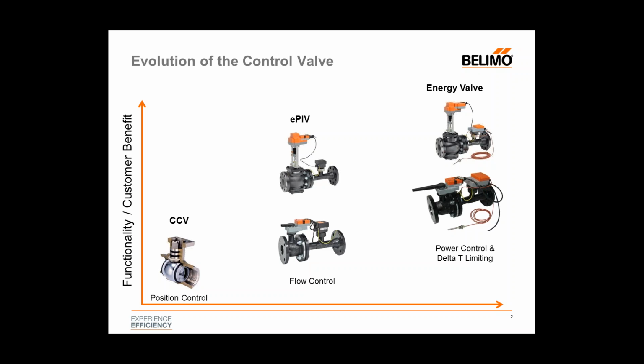So let's talk a little bit about valve evolution. In 1999, Belimo entered the control valve market with the characterized control valve. Primarily before that, Belimo was known as an air actuation company, but through a lot of the advances made in technology with air actuators, they saw a very good relationship to where they could apply it to control valves. Since 1999, we have sold more than 5 million characterized control valves with a very, very low return rate for quality. So it's something we've had very good success with, and it's a very stable product line for us.